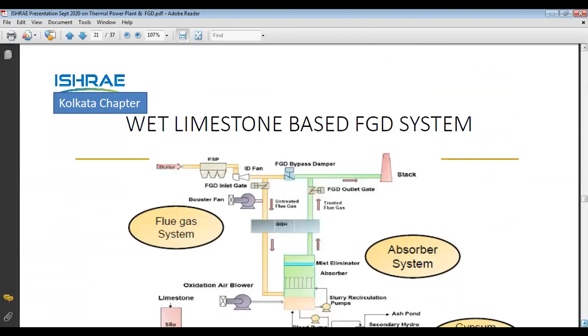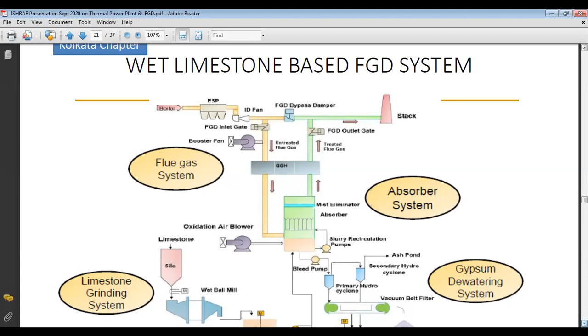This is the typical scheme of a limestone based FGD technology. In this system, limestone is utilized for the scrubbing. Limestone is available in the market in lump size, but for the reaction it is required at a certain size, as it is sprayed in slurry form. For that slurry, a limestone size of less than 44 micron is recommended. For that reason, the wet ball mill is installed. The limestone is fed to the wet ball mill, where the slurry is prepared, and this slurry is fed to the absorber. Basically, this is the system before FGD.